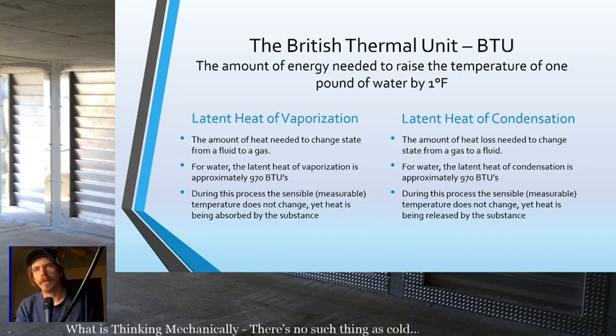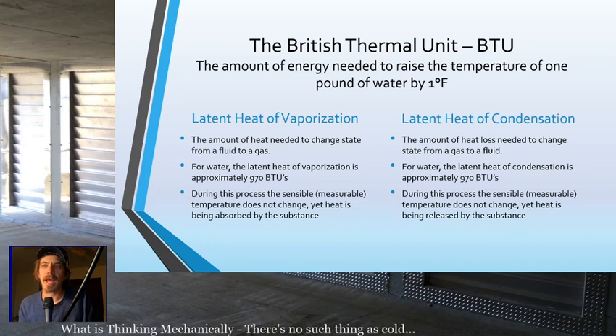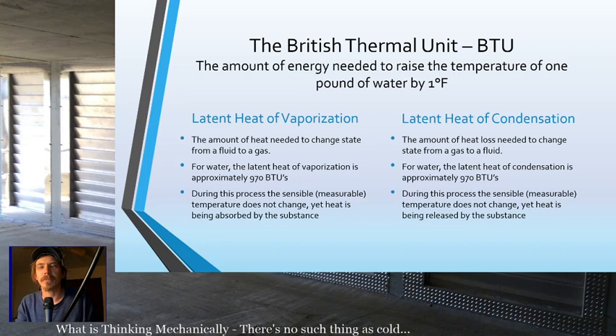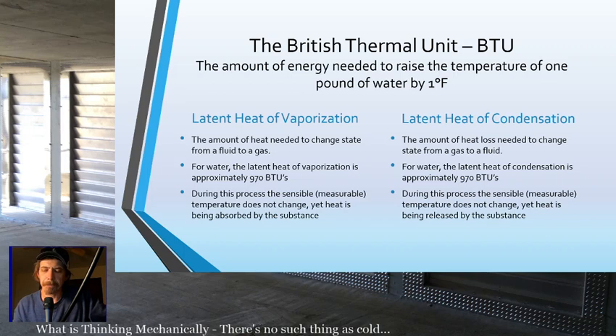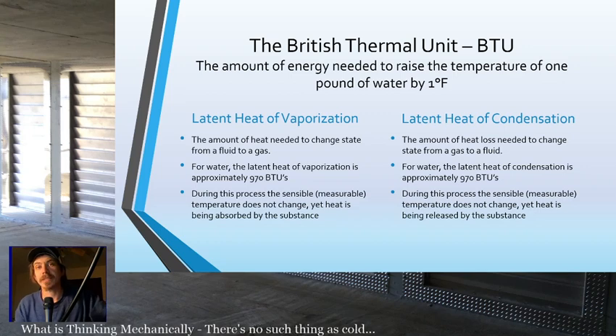And for water, that latent heat of vaporization is about 970 BTUs. So for every pound of water, we're going to have to add another 970 BTUs to turn that water into steam. It might not be actually a pound, but for purposes of presentation, it takes 970 BTUs to take that water from water to steam, and then once it turns into steam, we can add more sensible heat again. We can start to raise the temperature of that steam over 212 degrees Fahrenheit, but that water will never go above 212 degrees Fahrenheit until it's turned into steam. And during this process, the sensible measured temperature does not change. Just like I said, the water will stay 212 degrees Fahrenheit until that process is complete.